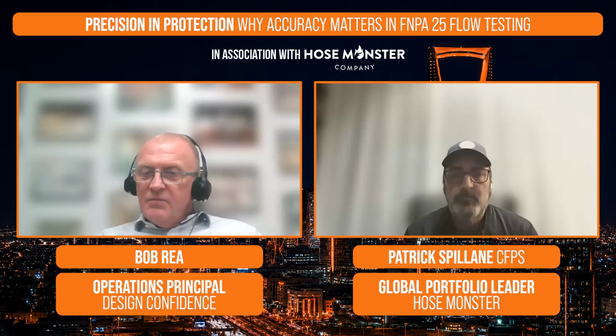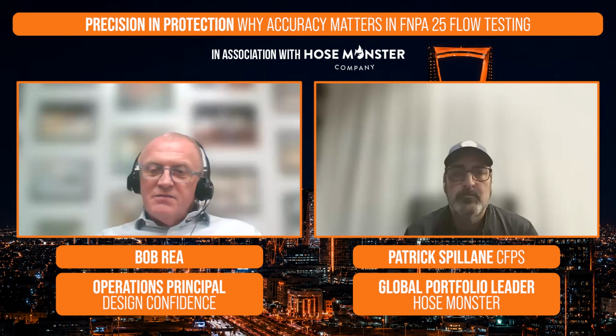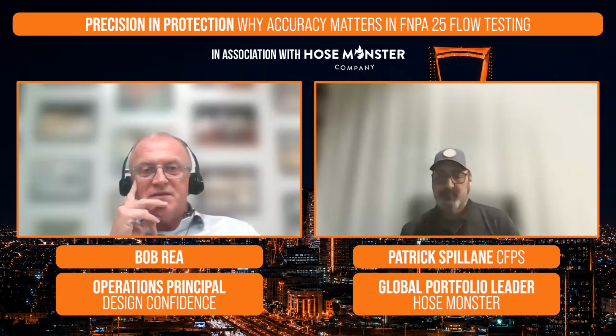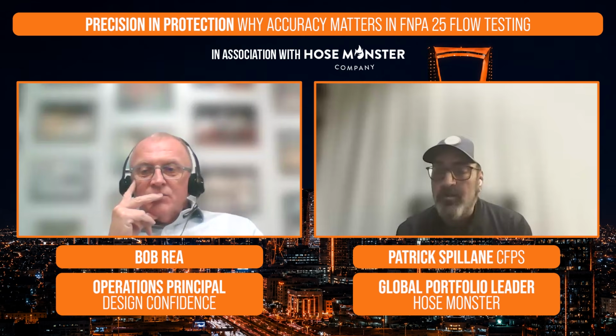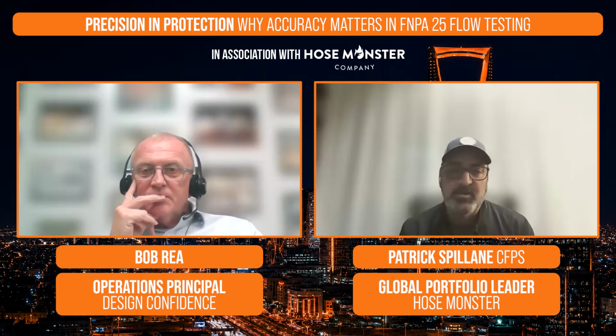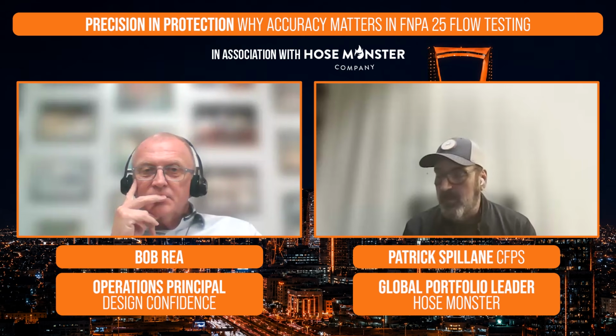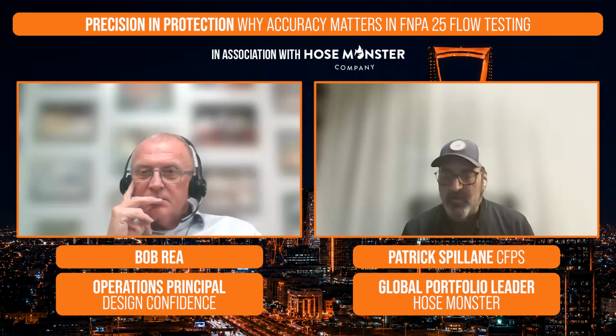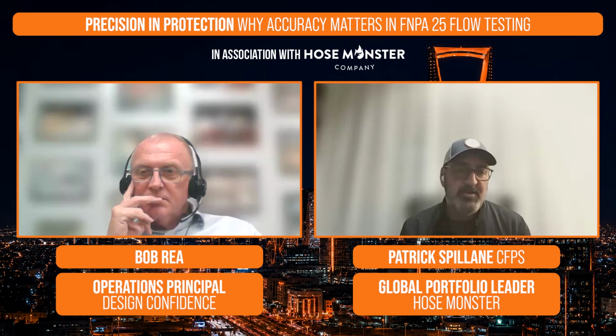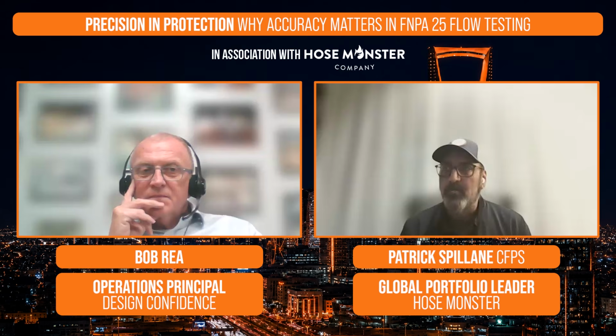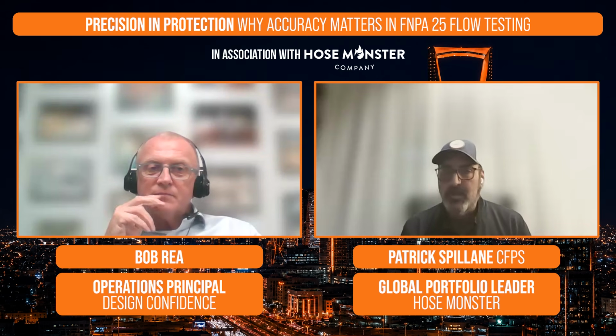Super. And then Rathanakara asks, does the equipment require periodic calibration? And if so, what's the duration? And who provides a calibration certificate? Yes. So all test gauges and a flow meter should be calibrated on an annual basis. All of our products are FM approved, right? But as well as outside of our FM approvals, making sure that our gauges are accurate. It doesn't matter if you're using an analog gauge or a digital Smart Monster gauge, those gauges should be confirmed to be within calibration every year. Same thing with flow meters as well too. The gauge on the flow meter needs to be calibrated.